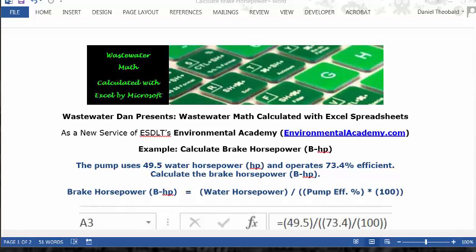this way: Brake horsepower equals water horsepower divided by pump efficiency percent times 100. That's essentially the decimal equivalent of the percentage described.